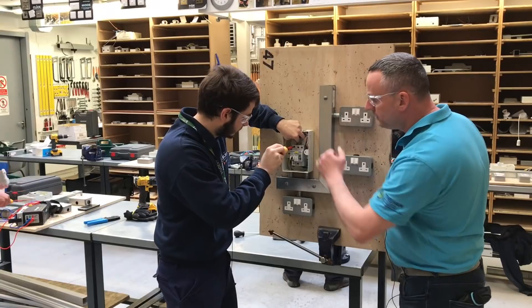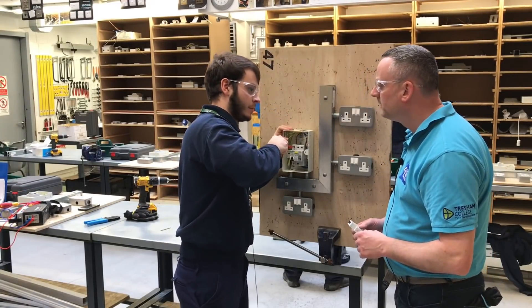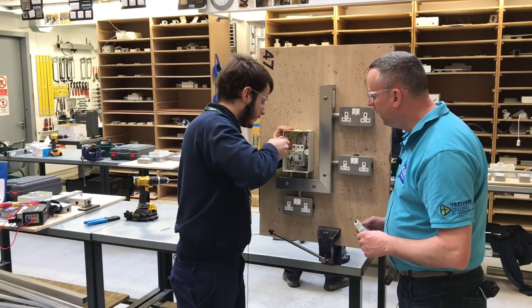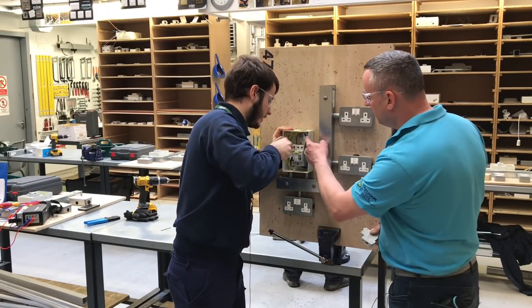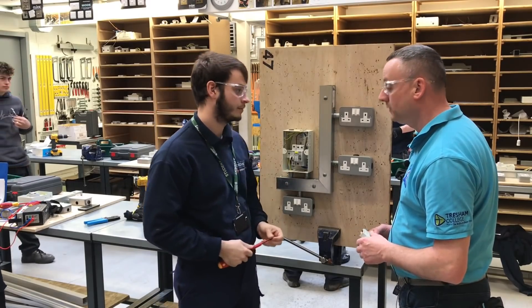Is it exactly the same for the neutral and earth bars, Ben? No, the neutral and earth bars are at 1.7 newton-metres of torque. So they're different. Where did you find that information for the neutral and earth bars? It comes in the instructions of the board.